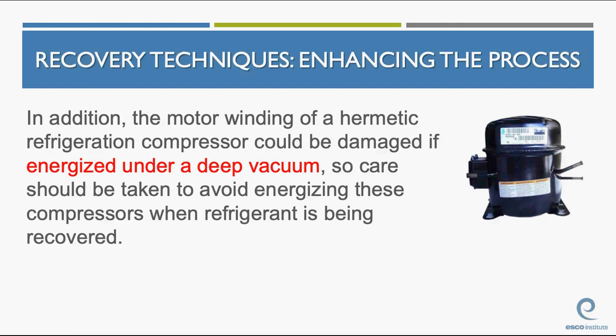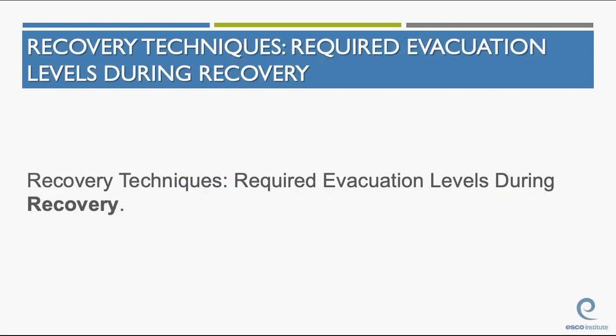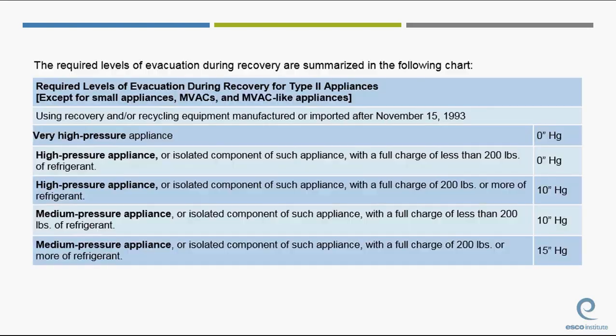Okay? It's for your own safety as well. Okay, we have required evacuation levels. That's how low we pull the pressures in a system that we're required to have during recovery. Okay, these are EPA regulations. There's a table, I believe it's on page 22 of your manual. Can somebody tell me if that's actually where it is? Correct. Okay, this table, guys, this is just another one you need to know.